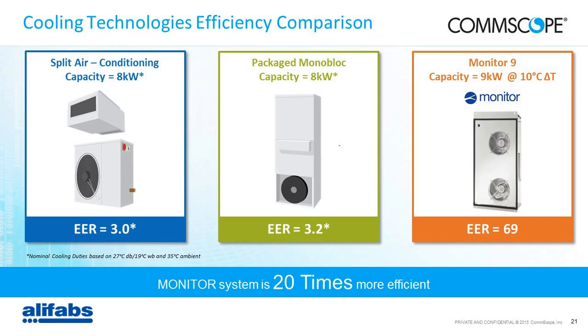Meanwhile, the packaged monoblock system will provide you with a free cooling system as well. But again, the ER is only gravitating on average at around about 3.2. And this is based on the EN 14511 standard figures. Meanwhile, if you look at the Monitor system with a delta T of 10 and a cooling capacity of 9 kilowatts, they deliver you an EER of 69. That's about 20 times more efficient.